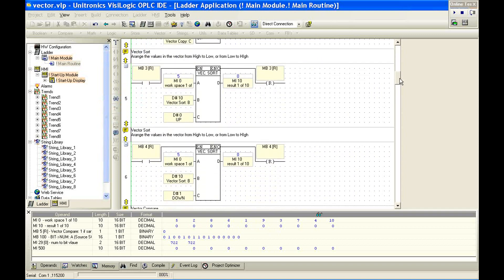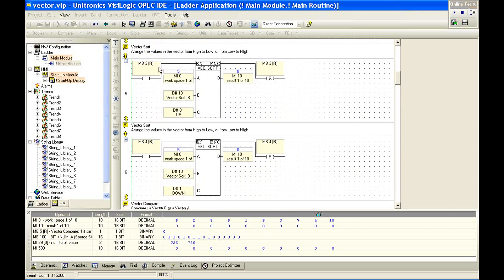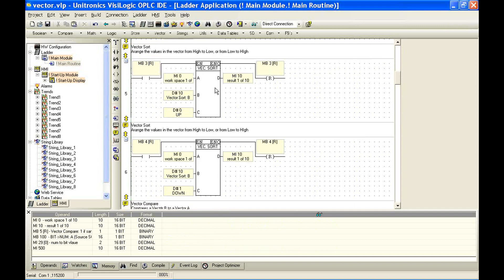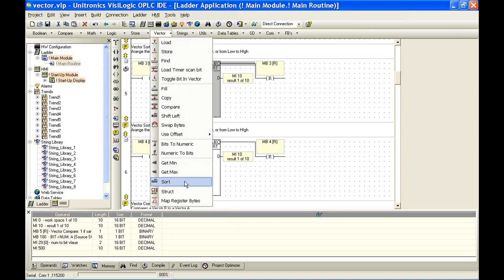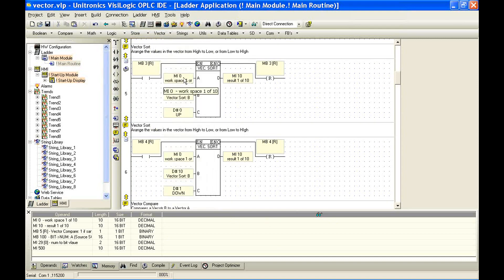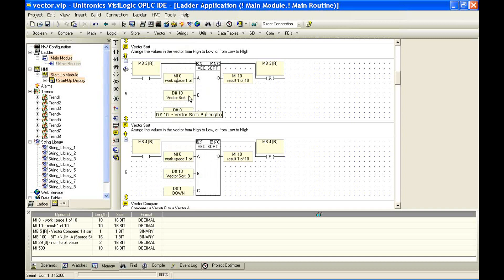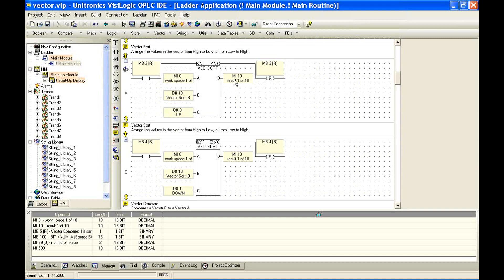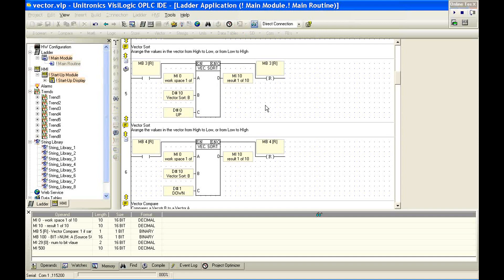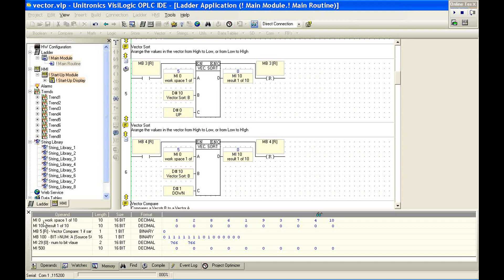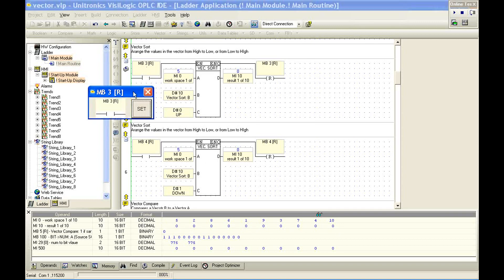Now that we have our data in some location, let's look at some tools we can work with. We have a vector sort function. The information that we give this function, we can double click here. Again, vector sort. The information we define here is our start address, MI0, which is our workspace, and the length is 10. And we can decide if we want to sort up or sort down. And the resultant location is going to be MI10. Again, this is not simply MI10. It's MI10, 11, 12, 13, 14, 15, 16, 17, 18, 19. So again, the length defined here is also what we're going to copy to the destination.